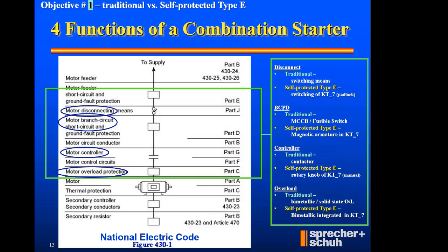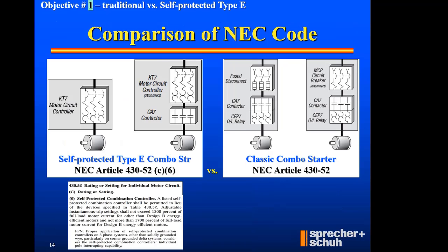And then lastly, the National Electrical Code says I need an overload for this circuit. How do we comply with that? On the right-hand margin, from a traditional sense, traditionals have to insert an actual overload connected to the load side of a contactor. That's how you comply. From a self-protected Type E compliance, there's integral thermal bimetallic overload protection built into the KT7. So it's in the device. Taking the code requirement and applying it, do I do a traditional? Do I do self-protected? That's what the comparison looks like on this page.